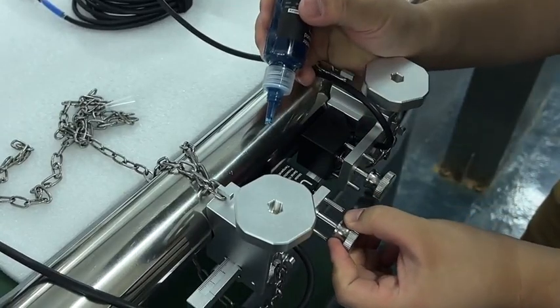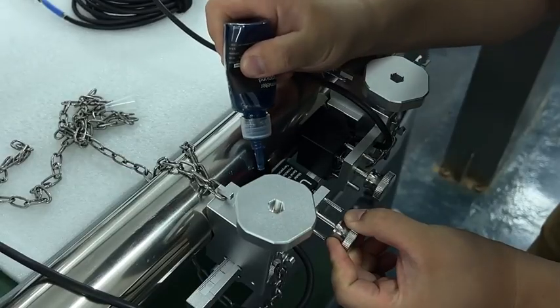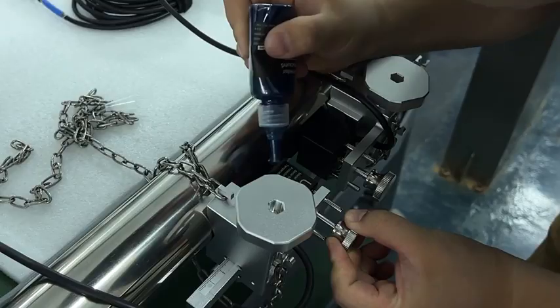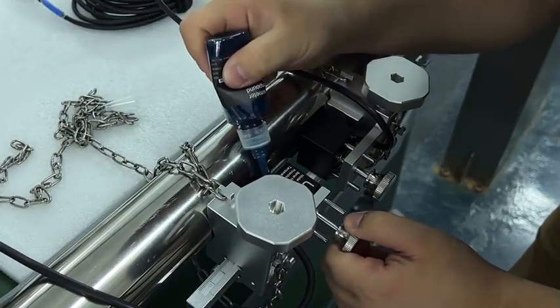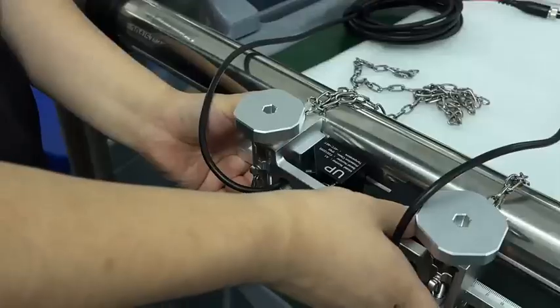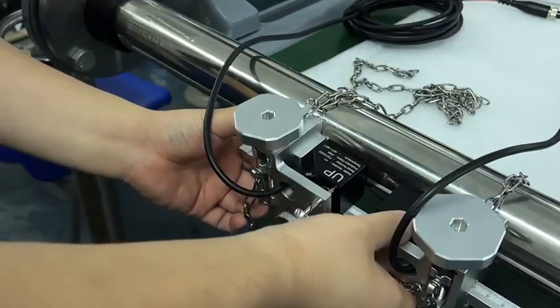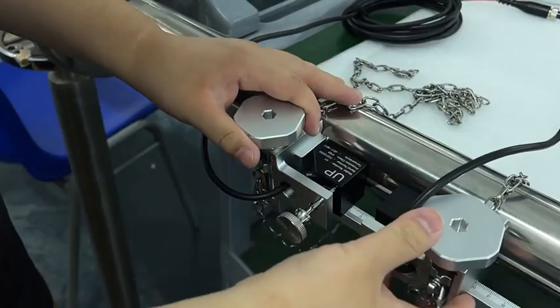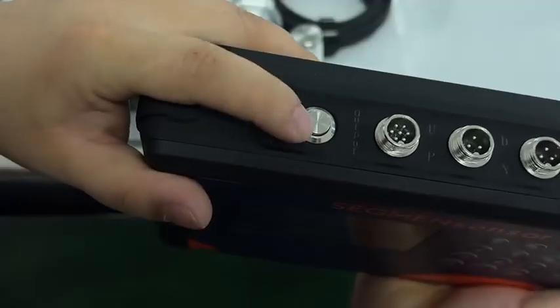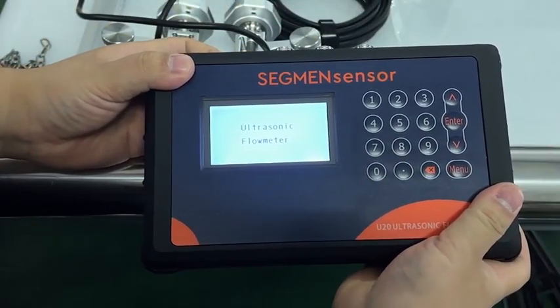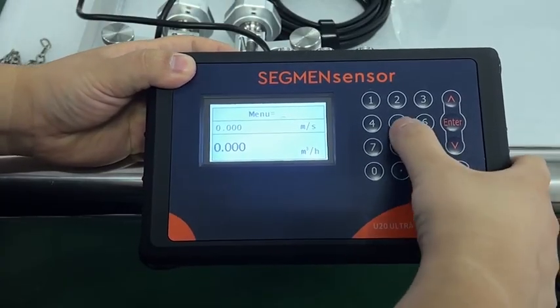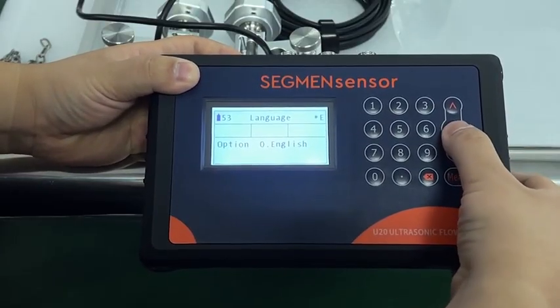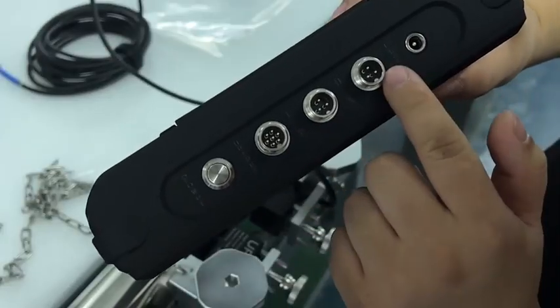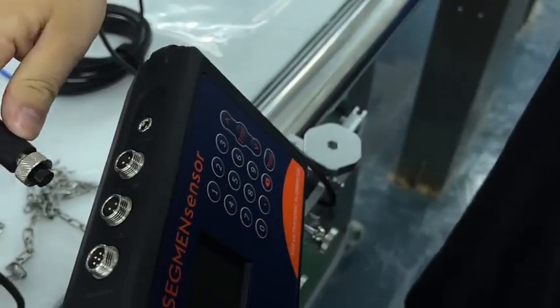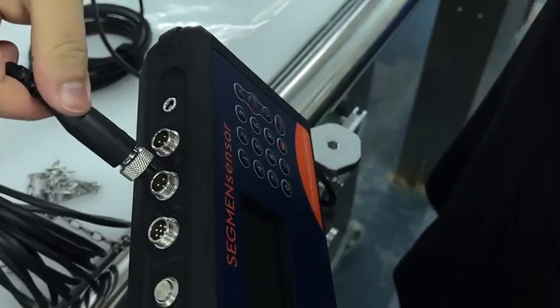With the chain secured, the transducer probes are positioned along the bracket rail. The mounting distance between probes is determined by a calculation that factors in pipe outer diameter, wall thickness, pipe material, and the speed of sound in the fluid. Each installation uses a documented spacing table to eliminate guesswork. Acoustic coupling gel is applied to the face of each transducer probe before final positioning. This gel fills the microscopic gap between the flat transducer surface and the curved pipe wall. Without the gel, ultrasonic energy reflects at the contact surface instead of transmitting into the pipe. A thin, uniform layer of gel is sufficient. Applying too much is as problematic as applying too little.